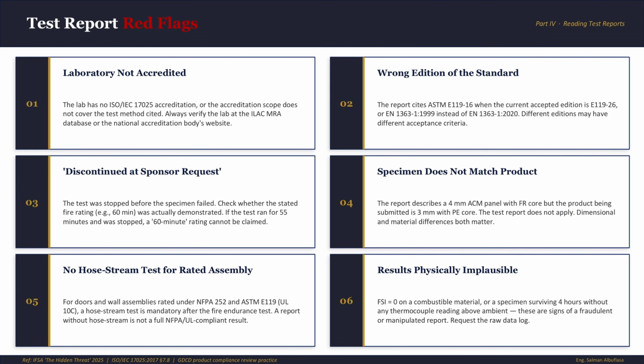This is not every reason to flag a report, but the possibility that you will encounter one of them is very high. First, the laboratory is not accredited, or the accreditation scope does not cover the specific test method cited in the report. Second, wrong edition of the standard. Let's say ASTM E119-16 done recently, at a time when the current accepted edition is the 2026 edition. That's a big no. Different editions carry different acceptance criteria. Always verify the edition is current and accepted by the authority having jurisdiction. You cannot accept older versions instead of new ones.